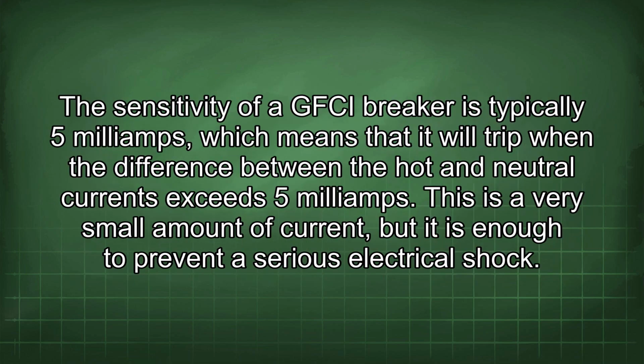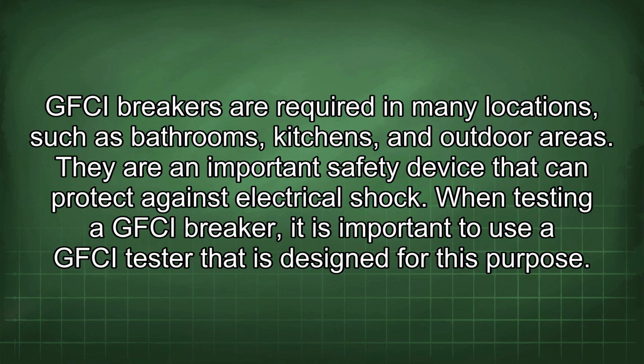The sensitivity of a GFCI breaker is typically 5 mA, which means that it will trip when the difference between the hot and neutral currents exceeds 5 mA. This is a very small amount of current, but it is enough to prevent a serious electrical shock. GFCI breakers are required in many locations such as bathrooms, kitchens, and outdoor areas. They are an important safety device that can protect against electrical shock.